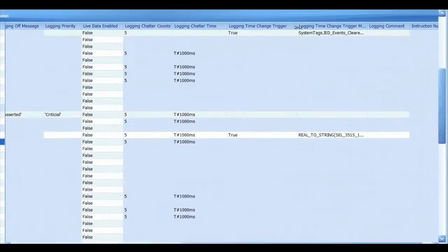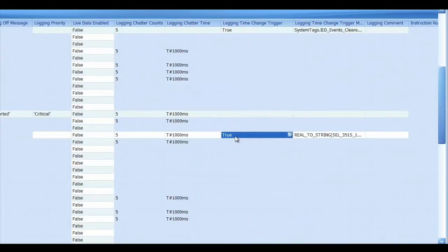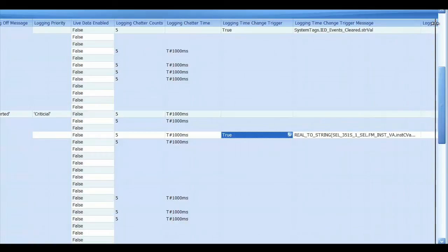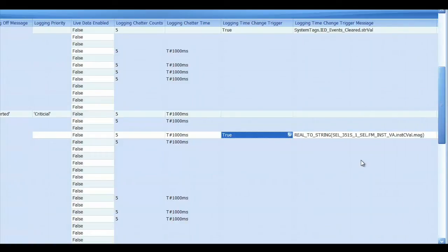So to do that I have this logging time change trigger. I set that to true. And then there's a logging time change trigger message. And that message will be logged any time the time changes. And the time will change when the value exceeds the dead band of that value. When the time changes, this is the message that will log.